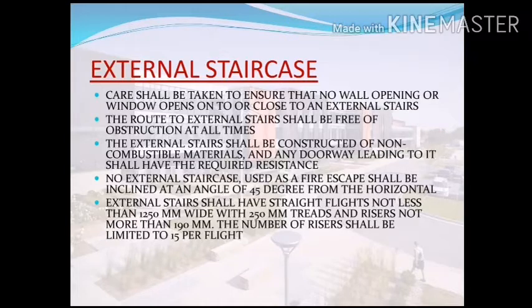The external stair shall be constructed of non-combustible material. In an earlier slide, we discussed combustible and non-combustible materials — combustible material is not fire resisting and non-combustible material is fire resistant. Any doorway leading to the external staircase shall have the required fire resistance. No external staircase used as a fire escape shall be inclined at a greater angle than 45 degrees from the horizontal.